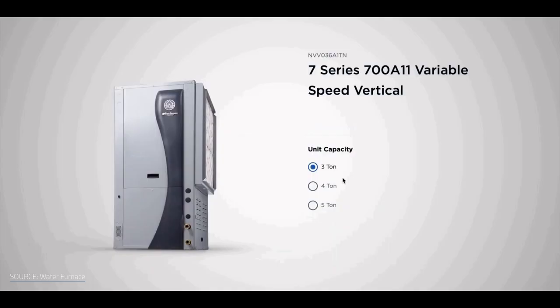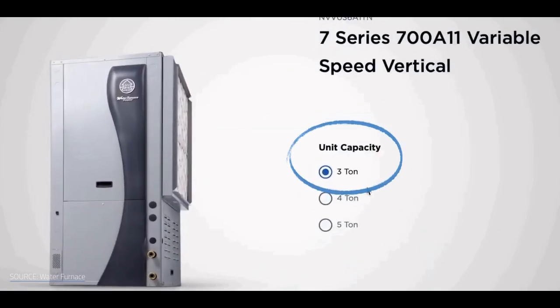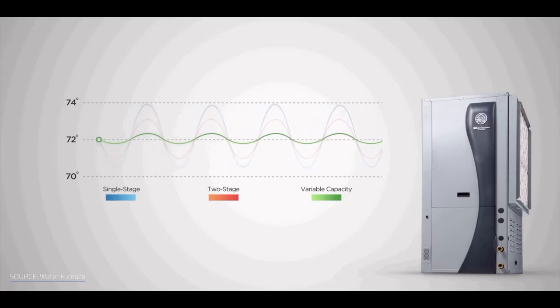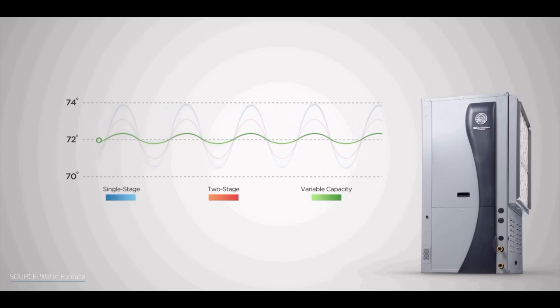Ideally we'd have something around a 2-ton system, but since we ended up going with the Water Furnace Series 7, the smallest available is a 3-ton system. The fact it's a little oversized shouldn't be an issue since it's a variable speed system and can easily run partial load demands. In fact, it might help us since it'll run at lower percentages most of the time, which should make for even quieter operation.